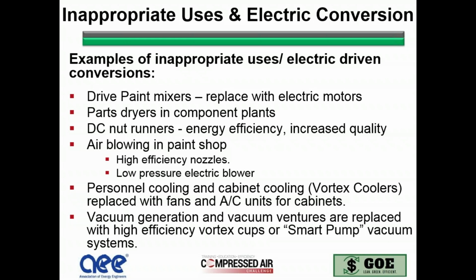Personal coolers: many people use air to blow on them because they feel it's cooler. I always have a concern, especially with oil systems, it's not very good to be breathing that in. Also to cool cabinets, so using vortex coolers, replacing them with fans or AC units for the cabinets really is a good idea, because again, you're not blowing air that has oil and mist in it into either cabinets or a person's breathing space, and it allows you to get rid of that high cost of energy.